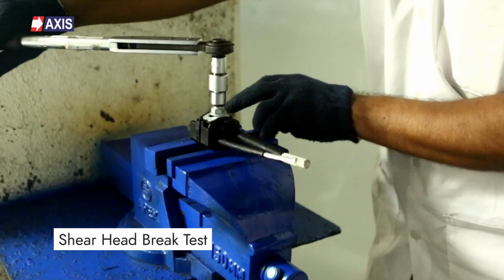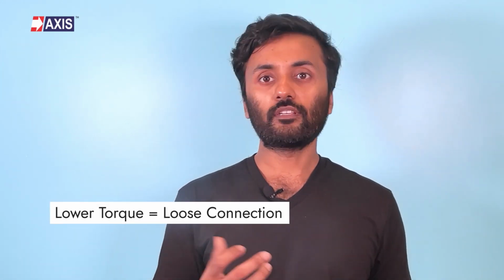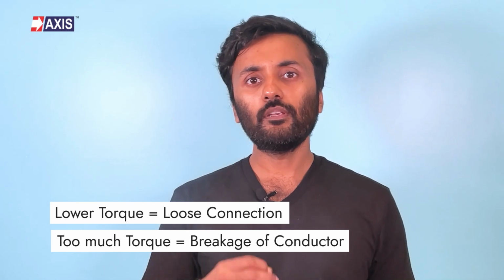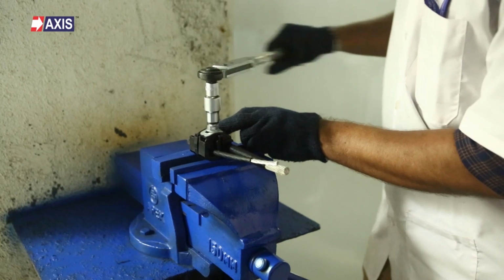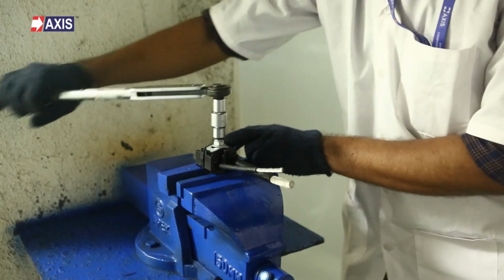Secondly, the shear head break test. The goal of this test is to ensure that the shear head breaks at a specific torque. This is important for the functioning of the IPC as it ensures and indicates correct installation. If lower torque is used, there will be a loose connection. If too much torque is used, it will lead to breakage of the conductor. Hence, if the torque is not accurate, it will lead to system failure. As you can see here, our IPC passed the test. Their shear head broke at the defined torque, which was between 9 and 11 Newton meters for this model.